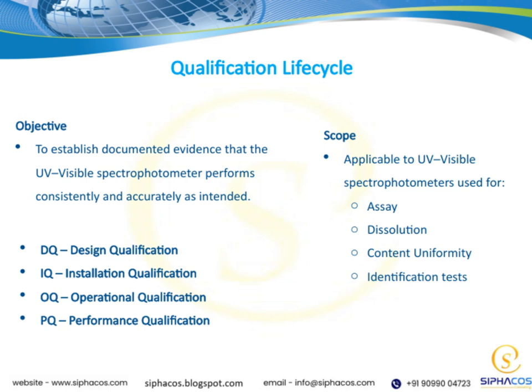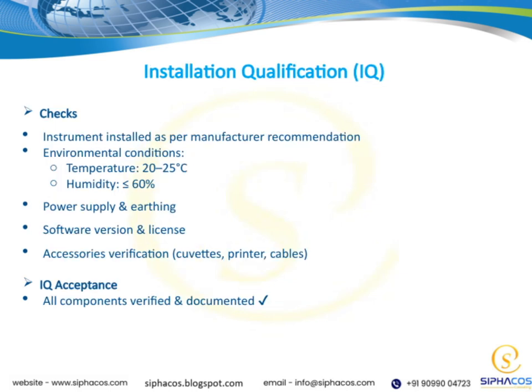Next, let's touch on the qualification lifecycle, which is a structured approach to validation. It starts with design qualification, or DQ, where we verify that the instrument design meets our needs. Then comes installation qualification, IQ, ensuring the device is installed correctly. Operational qualification, OQ, tests that the instrument operates properly within specified parameters. And finally, performance qualification, PQ, confirms that the device performs reliably during routine use. Together, these steps help us ensure that our equipment is always up to standard, supporting our overall goal of delivering high-quality, consistent results. Now, let's talk about the installation qualification, or IQ, checks.